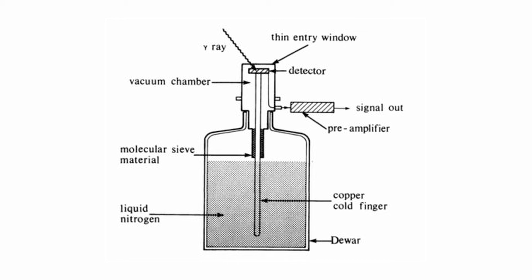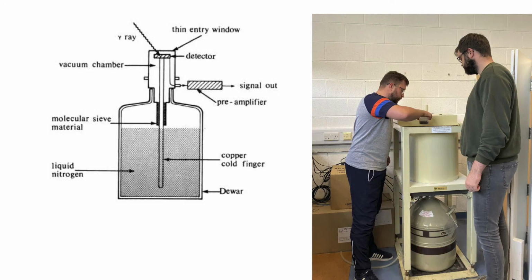So when in operation then, on a weekly basis, we have to pump liquid nitrogen from a dewar that's over here somewhere into this dewar. And there is lead shielding around here. This is just to suppress or try to minimize any of the background gamma emissions that exist in the air. And this is a top-loading system.